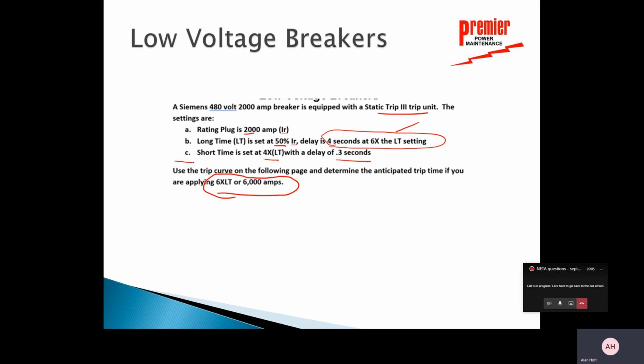But I forgot to look at this section down here. Short time set at 4 times pickup. So short time is set at 4,000 amps. And it's set for 0.3 seconds. So I don't even need to look at the curve. I know that this breaker should trip in about 0.3 seconds. Unless I did something to disconnect the short time, I'm hitting that short time limit.